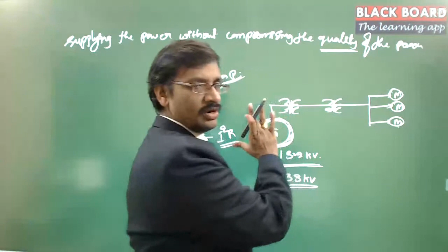Because of the insulation capacity needed, we try to use power at lower voltage here too - usually 11 kV, 33 kV, or 13.2 kV for higher capacity motors. Most household purpose motors use 440 volts, line to line value.